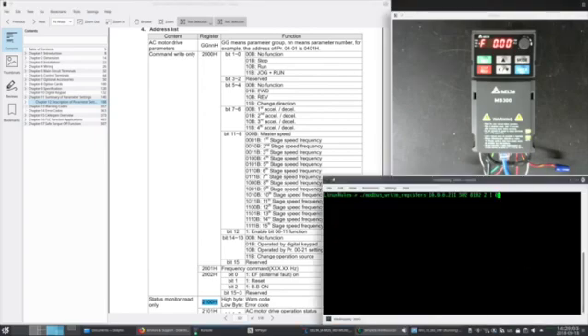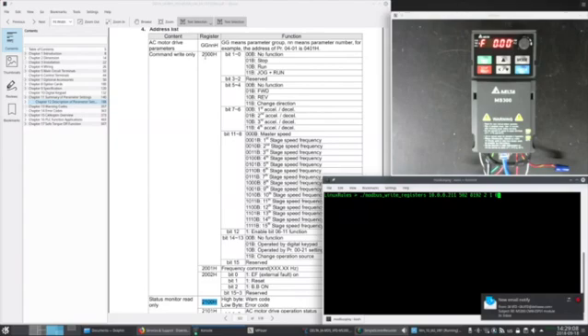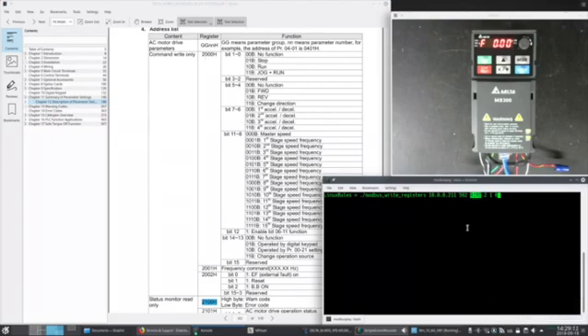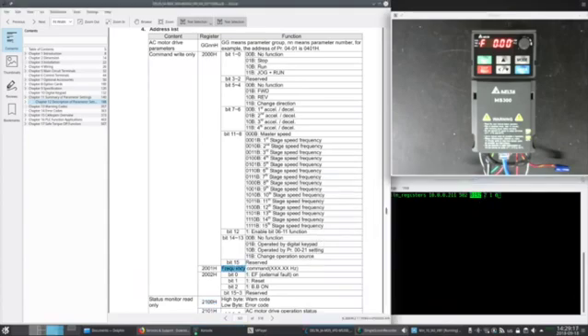My test tool takes the addresses in decimal. So I'm going to convert the 2000 hex. That comes up here as 8192. I'm going to write to two consecutive registers. That'll be 2000. And also I'm going to send it the frequency command in the next register.